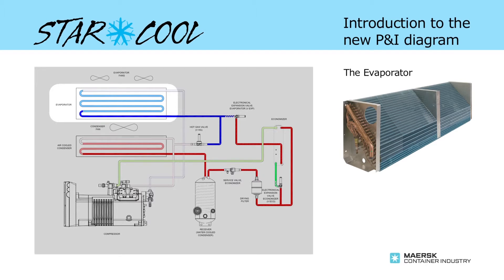Located below the evaporator are the six heaters. These have a capacity of 750 watts each and are in use during defrost. They are also activated when the cargo setpoint temperature is higher than the control temperature, and during dehumidification.